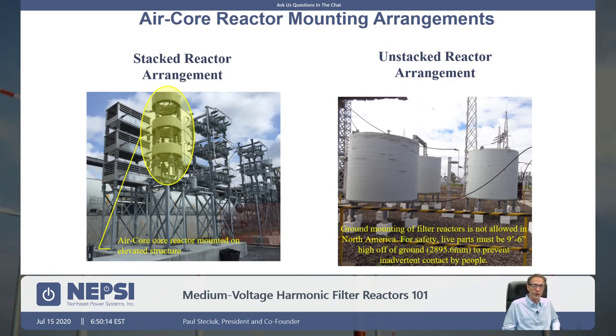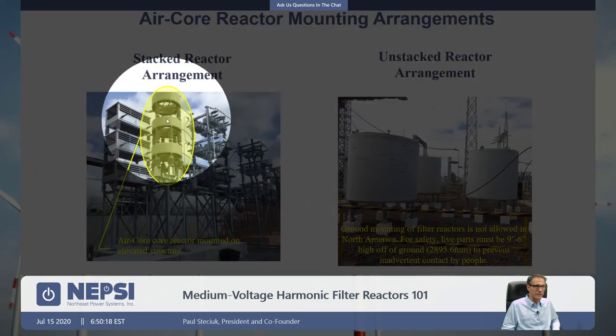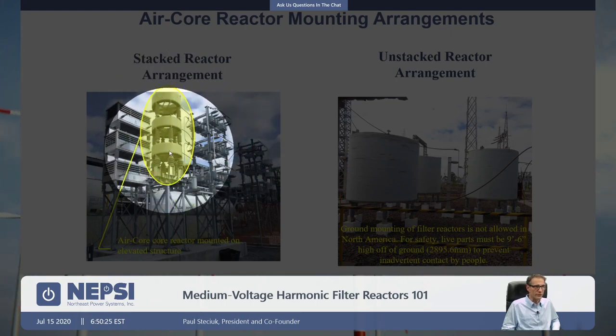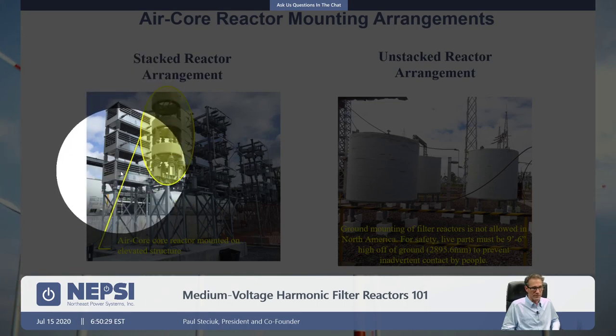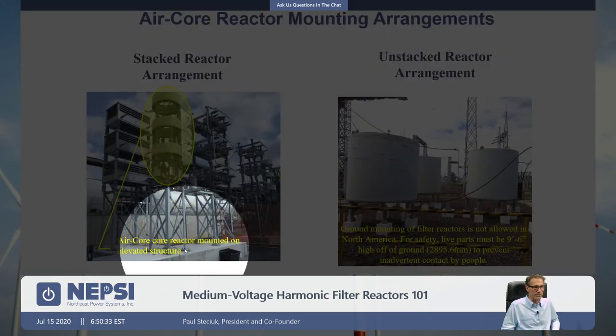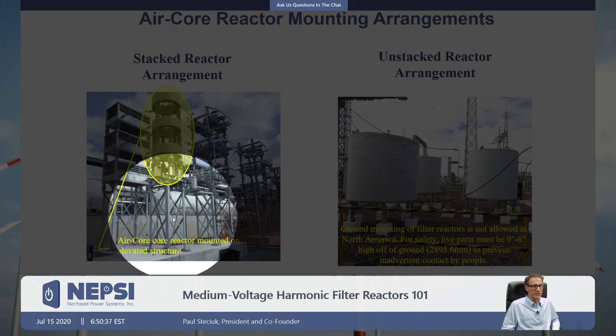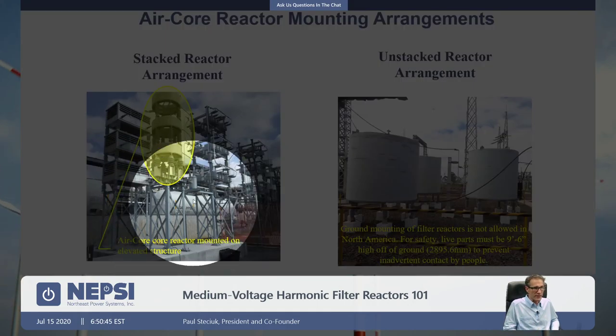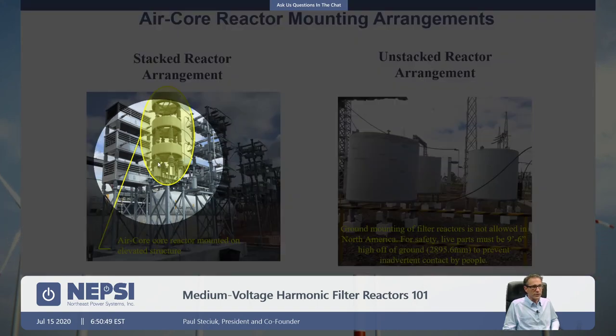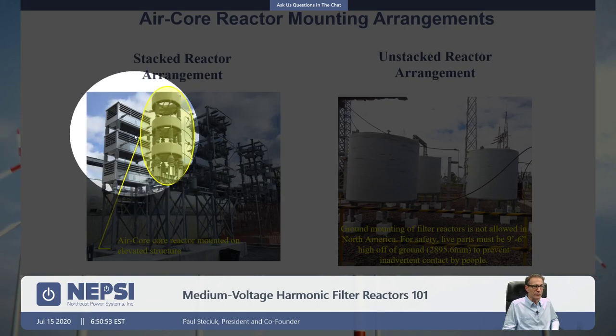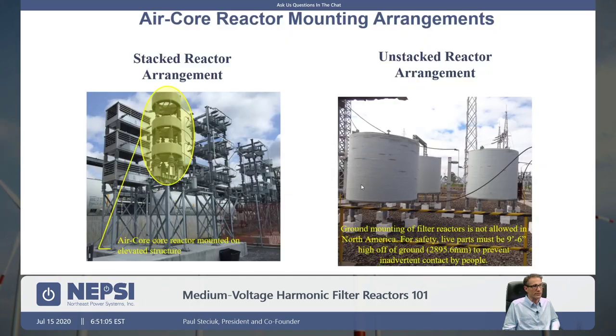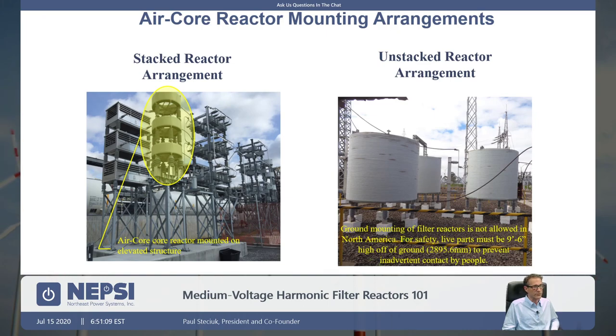For air core reactors, the picture on the left shows a stacked three-phase reactor. This is a high-pass filter — you can see a capacitor rack, reactors at three phases, and a resistor cage. Reactors in North America must be mounted on an elevating structure — approximately nine feet six inches (about three meters) of height is required so a person standing on a slab cannot touch live parts. The picture on the right shows reactors mounted at ground potential — from South America where they mounted those reactors at ground potential in an unstacked arrangement.